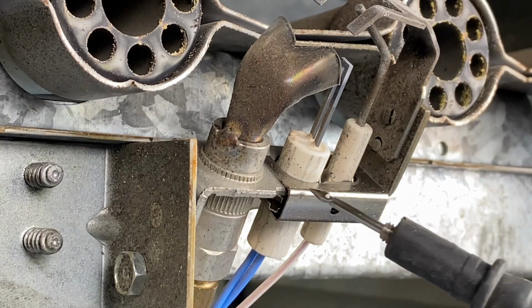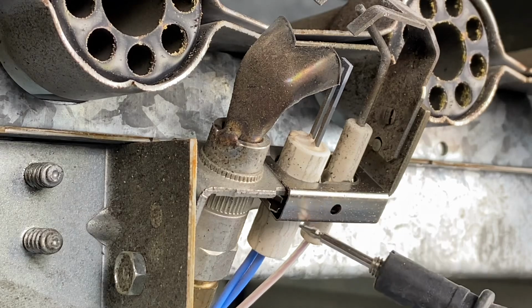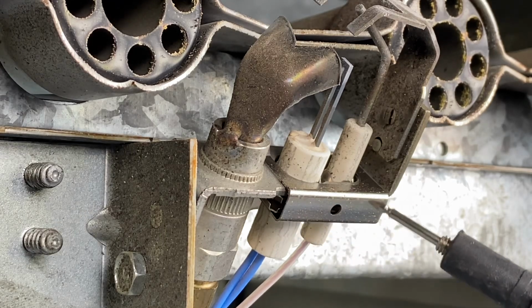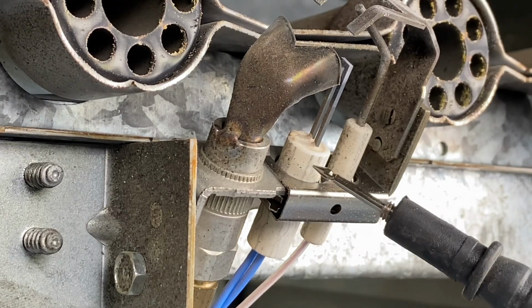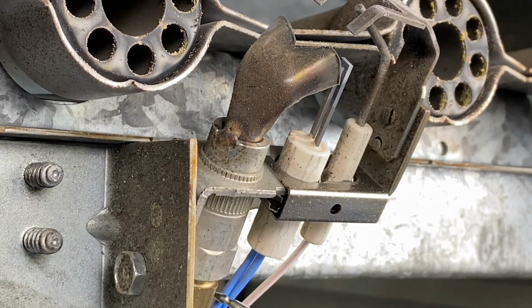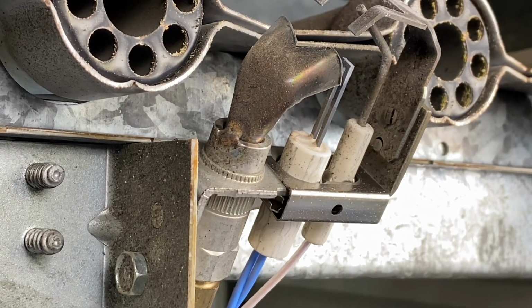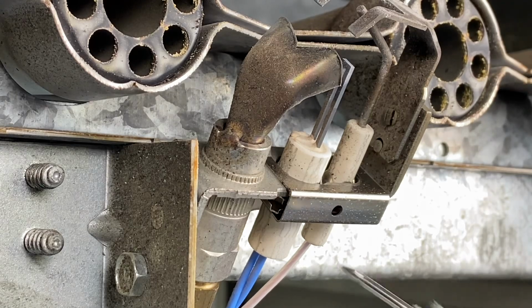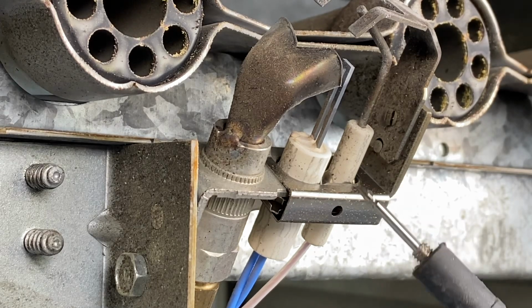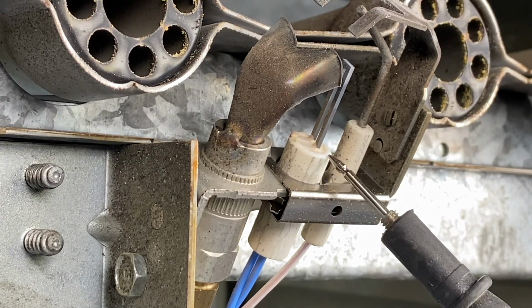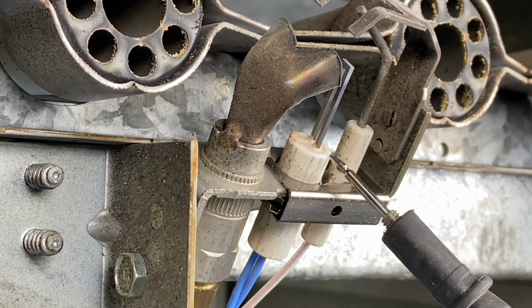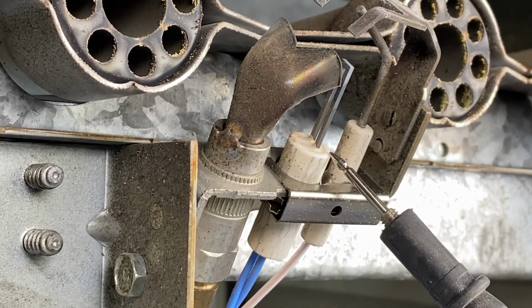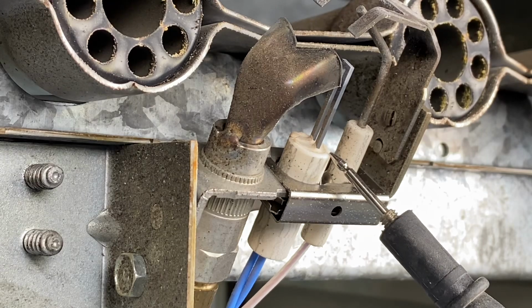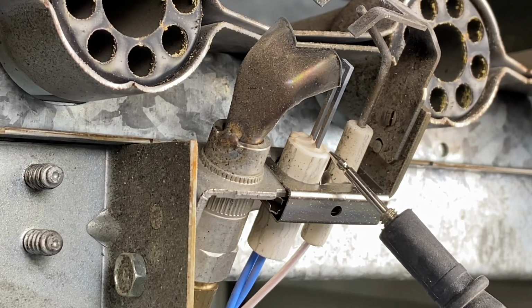This whole little assembly, see this little piece right here, will actually unscrew and pop out separate, and we can replace the hot surface igniter and the flame sensor. It includes the wires and the plug for the combination gas valve as an entire kit. I used to keep these on my service van, and when I came across these broken, we would replace them. Typically these lasted about 5 years in general, but sometimes they last a lot longer and sometimes not nearly as long.